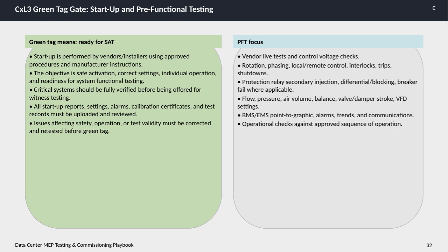The pre-functional testing, or PFT, focuses on several key areas. Vendors perform live tests and control voltage checks, ensuring proper equipment rotation, phasing, and confirming that local and remote controls, interlocks, trips, and shutdowns operate correctly. Protection relays undergo secondary injection tests, differential and blocking checks, and breaker fail tests where applicable. We also measure flow, pressure, air volume, and system balance, while verifying valve and damper stroke, as well as variable frequency drive settings. Building and energy management system points are checked for proper graphics, alarms, trends, and communications. Finally, operational checks are conducted to confirm everything aligns perfectly with the approved sequence of operation. This thorough process ensures that systems are safe, functional, and fully ready before moving on to the final acceptance stages.